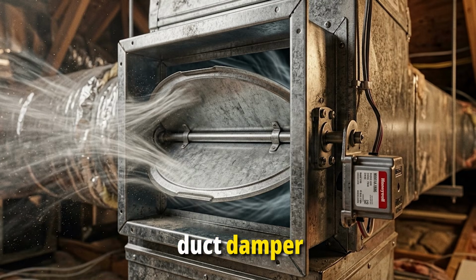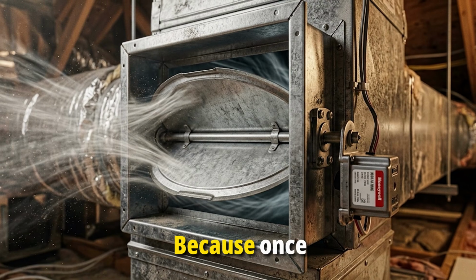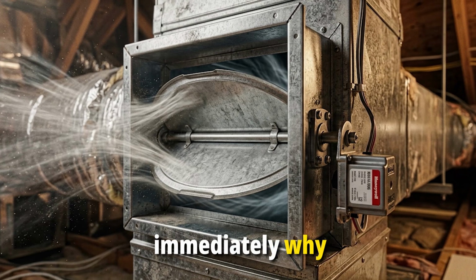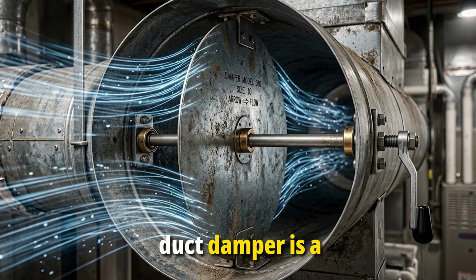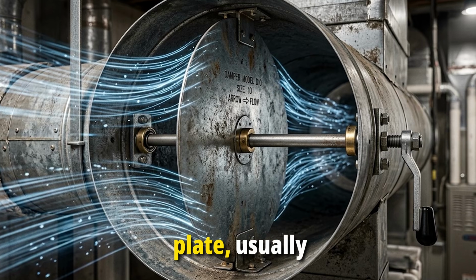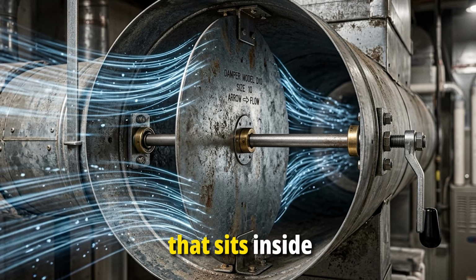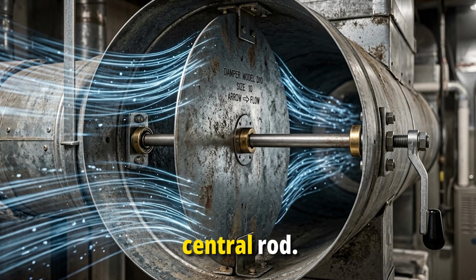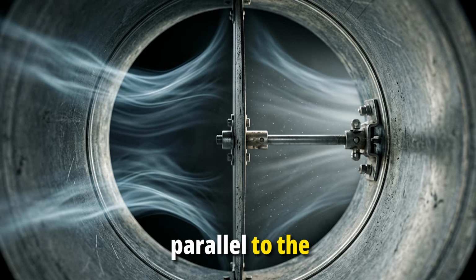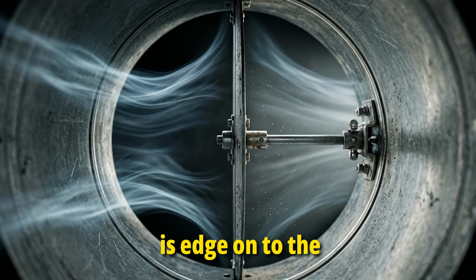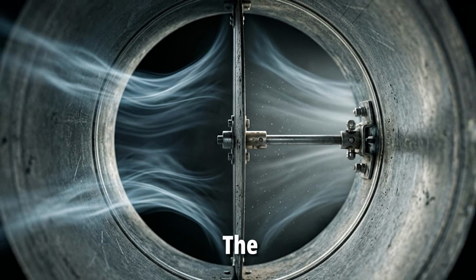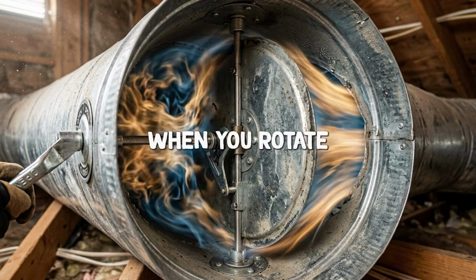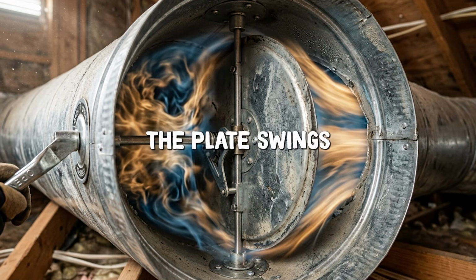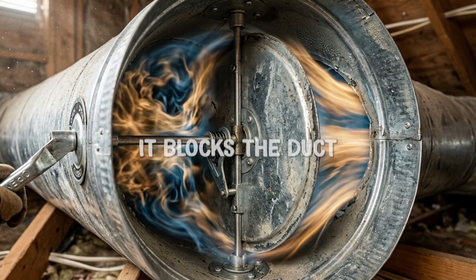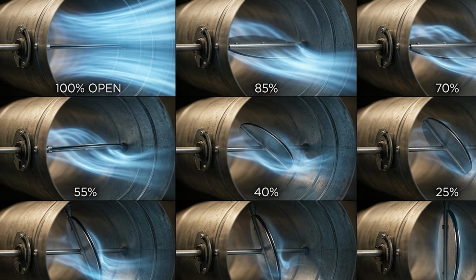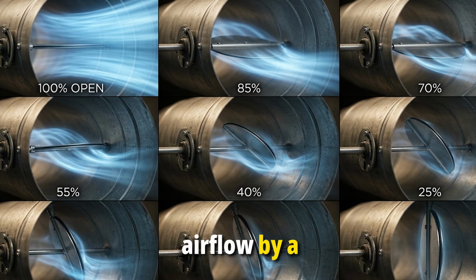Let me tell you what a duct damper actually is, because once you see it, you will understand immediately why it matters. A duct damper is a round metal plate, usually galvanized steel, that sits inside a round duct and rotates on a central rod. When that rod is parallel to the duct, the plate is edge-on to the airflow. Air passes freely. The damper is fully open. When you rotate the rod a quarter turn, the plate swings perpendicular to the airflow. It blocks the duct almost completely. Every position in between restricts airflow by a different amount.